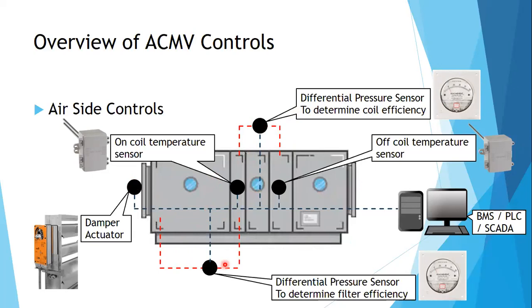So this sensor, the pressure differential sensor, is determining the pressure difference between filters. Usually your filter manufacturer will say this filter has a pressure drop when the air passes through, so that we can capture all this dirt or all these particles. This pressure drop will be 100 Pascal. But over time this dirt will accumulate, so your pressure drop will increase. The manufacturer will say up to 250. When your pressure drop is 250 Pascal, it means you need to replace your filter.